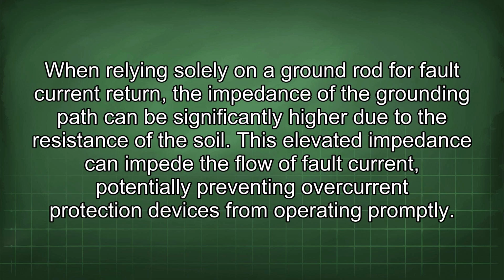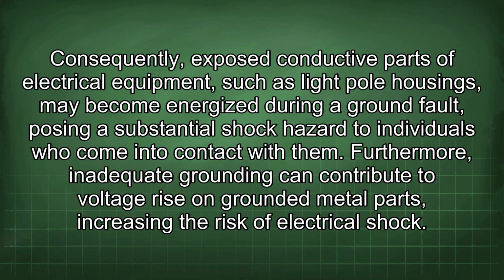When relying solely on a ground rod for fault current return, the impedance of the grounding path can be significantly higher due to the resistance of the soil. This elevated impedance can impede the flow of fault current, potentially preventing overcurrent protection devices from operating promptly. Consequently, exposed conductive parts of electrical equipment, such as light pole housings, may become energized during a ground fault, posing a substantial shock hazard to individuals who come into contact with them. Furthermore, inadequate grounding can contribute to voltage rise on grounded metal parts, increasing the risk of electrical shock.